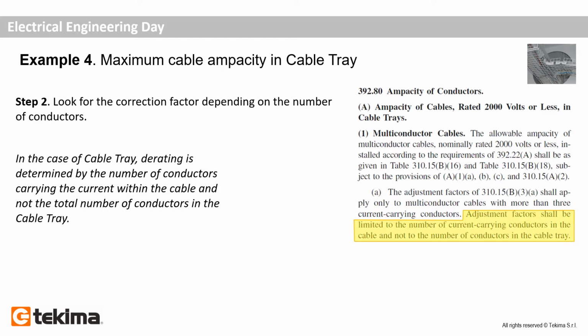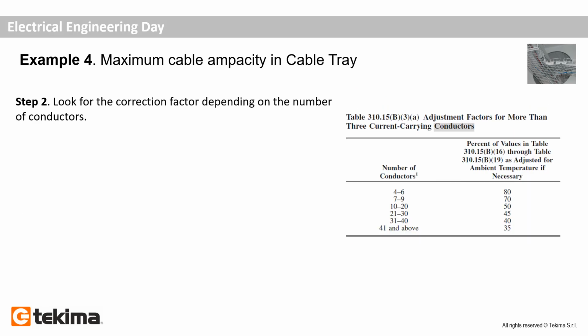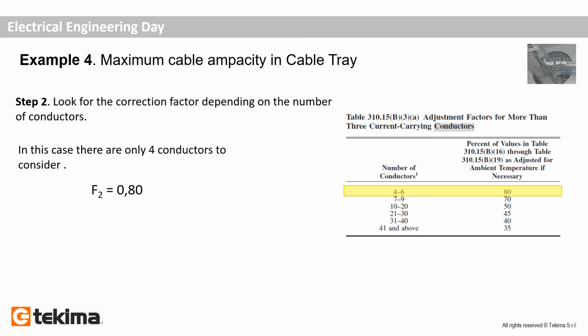According to the NFPA 70, the adjustment factor will be limited to the number of current carrying conductors in the cable and not the number of conductors in the cable tray. So the adjustment factor that takes into account the conductors grouping in the cable tray is completely different with respect to the adjustment factor for the conductors grouping used in the raceway. Considering this rule, the number of conductors carrying the current in the cable is 4, which means that the adjustment factor in this case will be 0.8.